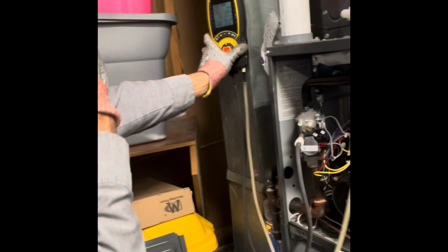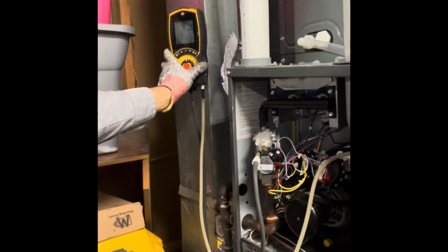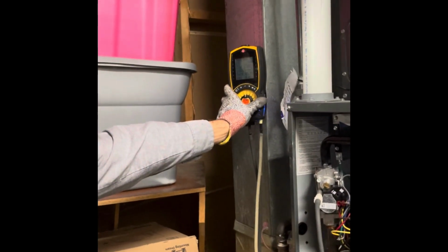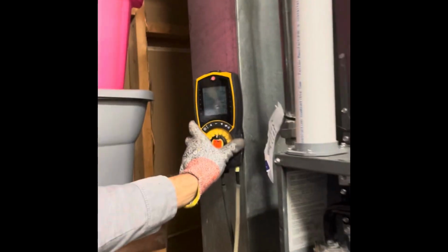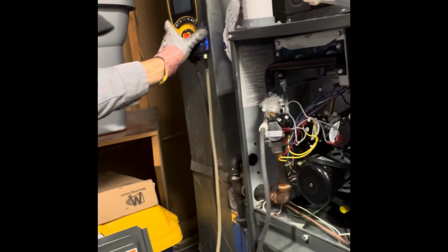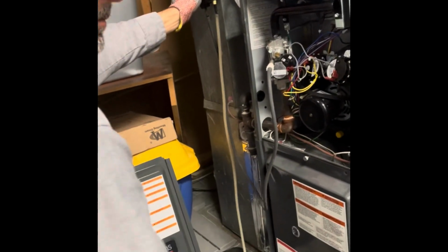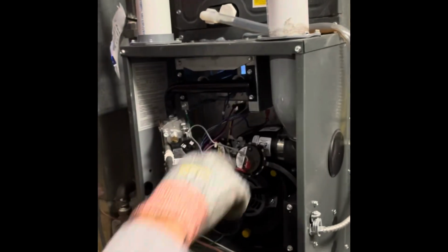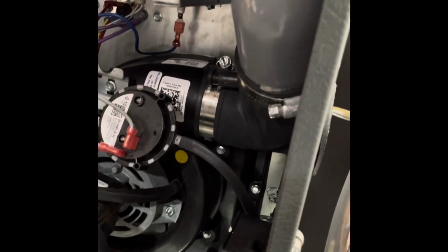In the meantime, we'll double check that CO number. So 74 parts. It went up 1 part, 2 parts. So I'm going to put us here at 75 parts per million. You want to take the tube out. Always make sure you're putting your rubber plug back in, because condensation is going to drip from here, and it is a very tight fit on that fitting there. The returning air is coming in at 77.